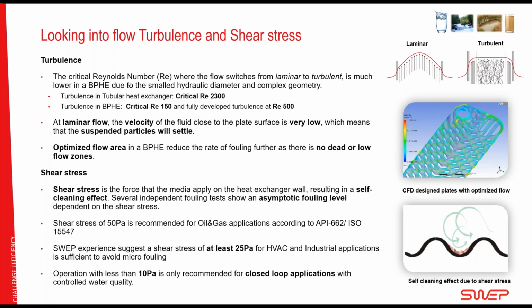So the critical Reynolds number in a brazed plate heat exchanger from laminar to turbulent is much, much lower than in a tubular heat exchanger. And that is because the brazed plate has a smaller hydraulic diameter and a much more complex geometry that is inducing turbulence. So in a tubular heat exchanger with a smooth pipe, the switch from laminar to turbulent is about 2,300. And in a brazed plate, we have a critical of about 150, and then it moves over to fully turbulent at about 500.